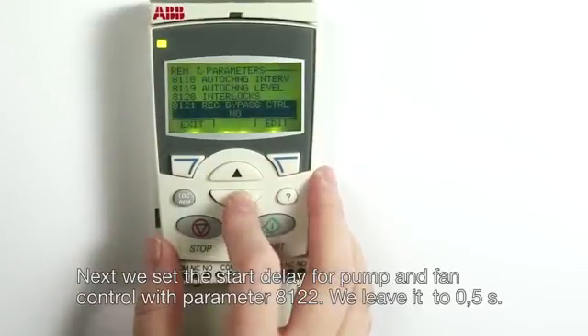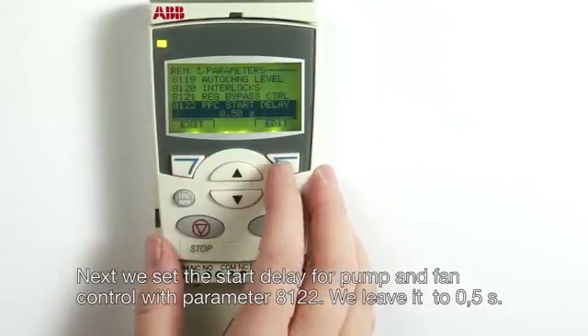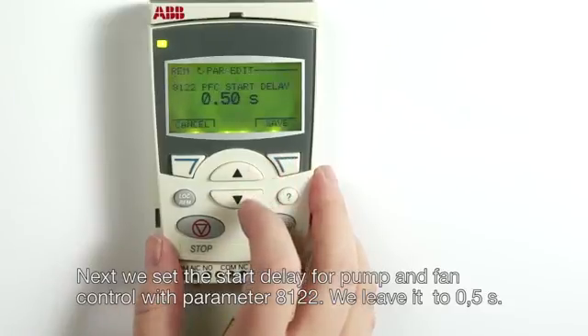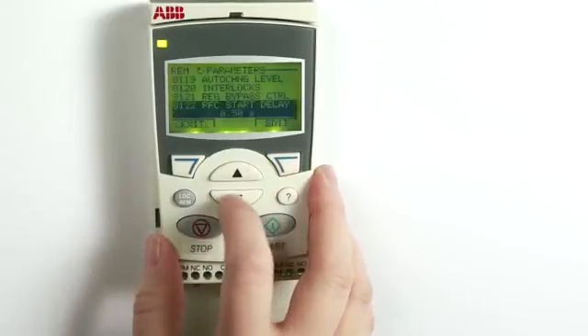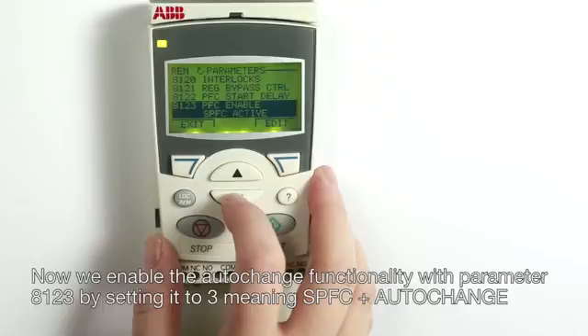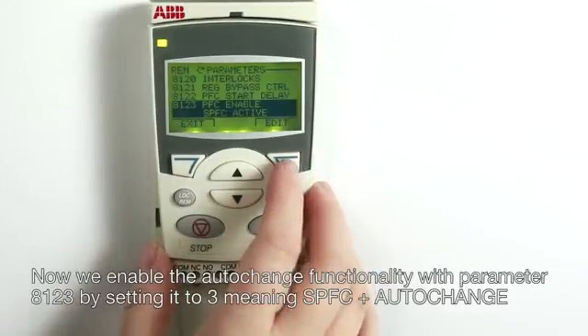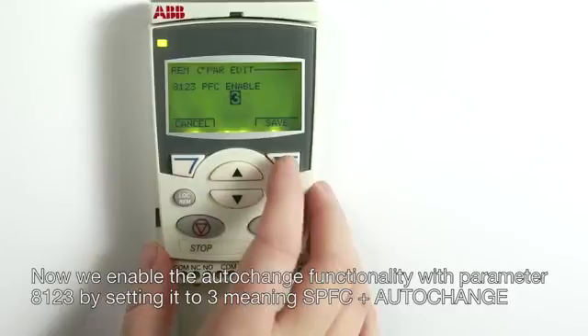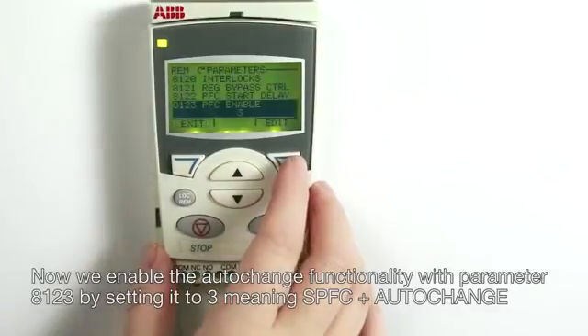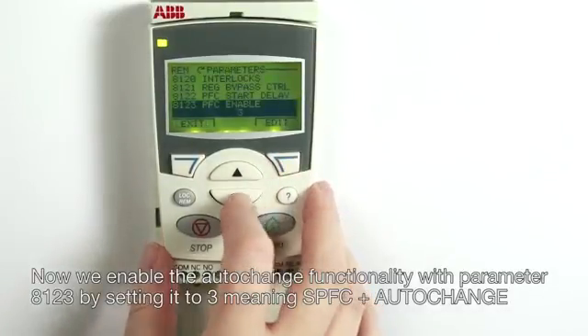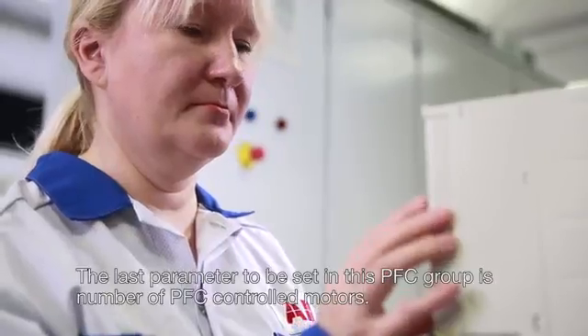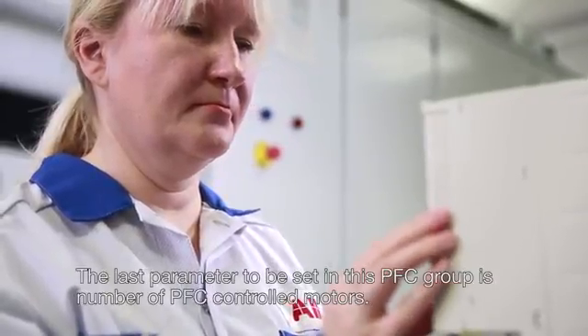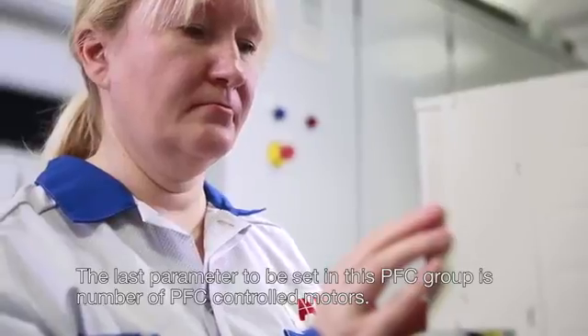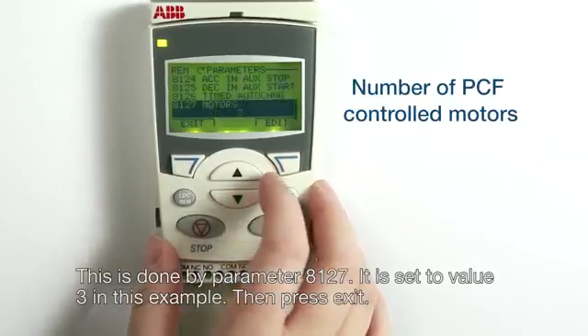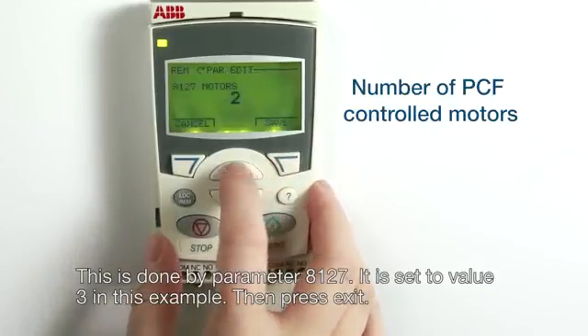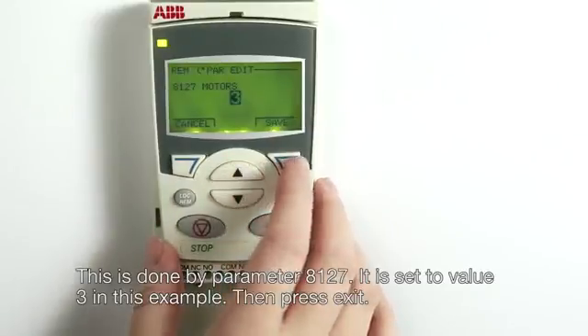Next, we set the start delay for pump and fan control with parameter 8122. We leave it at 0.5 seconds. Now we enable the auto change functionality with parameter 8123 by setting it to 3, meaning SPFC plus auto change. The last parameter to be set in this PFC group is the number of PFC controlled motors. This is done by parameter 8127. It is set to value 3 in this example.